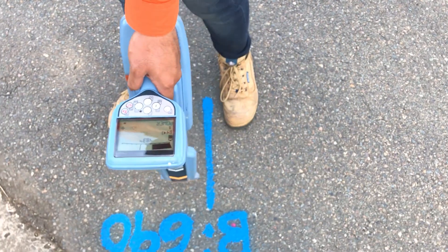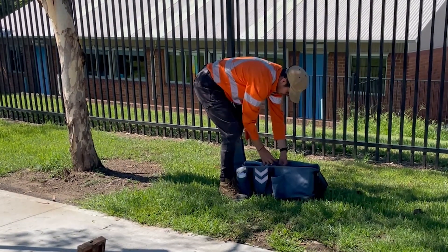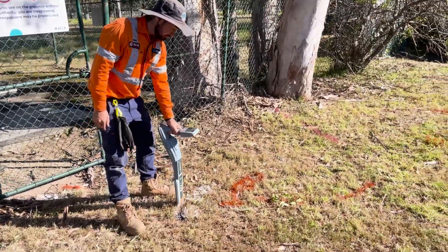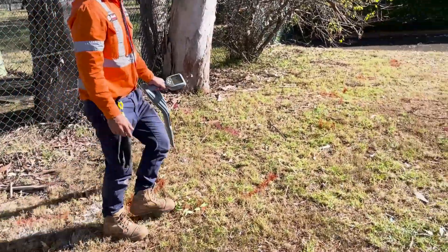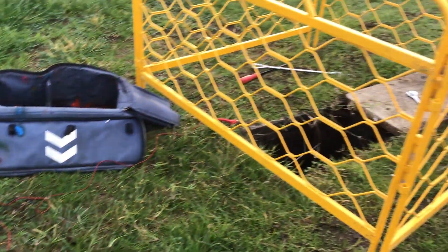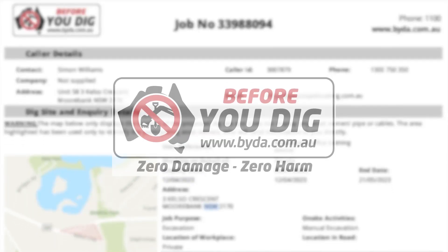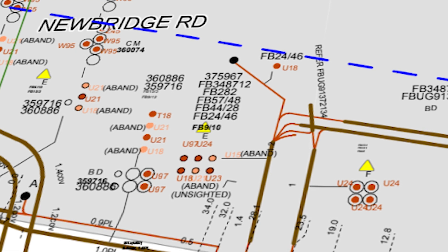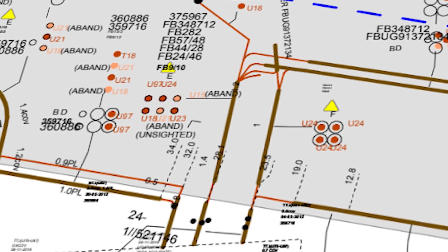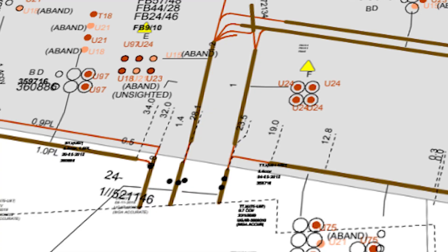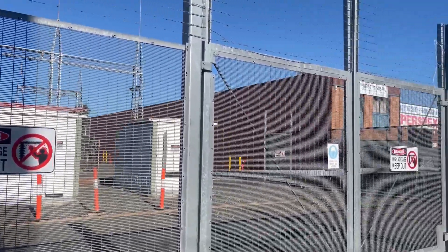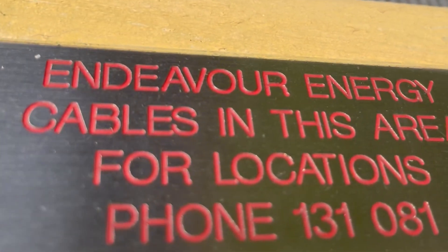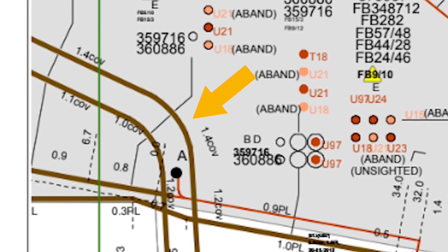Now that we know this, we can better understand how to deploy this method of locating out in the field. Passive won't typically be the first step you take on site, but on odd occasions it may be used to quickly identify what might be around so you can carry on with the active locating methods. The first thing you should do is submit a before-you-dig request to get back the main asset owner's utility drawings, including the electricity plans.